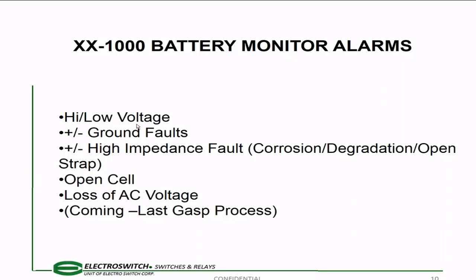The battery monitor alarms are, again, high-low voltage, positive and negative ground, and high impedance fault. The high impedance fault is going to be indicative of corrosion. You could have degradation of your cells, or an open strap, a loose strap. With ripple voltage and ripple current, as your impedance increases, your ripple voltage is going to go up, and your current would be going down as the battery ages. If you have a step change, where you go above 200 millivolts and below 10 milliamps, that means you have a problem with your battery, so you go check your battery. It could be corrosion or a loose strap. And if the current went down to 0, you have an open cell. If you check your battery and it has none of those, then you go to the AC filter caps, because you're probably degrading there.